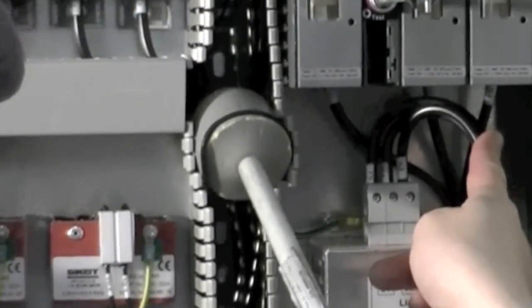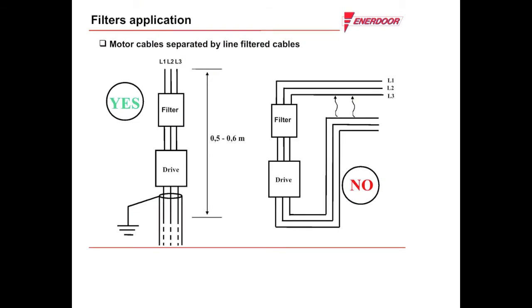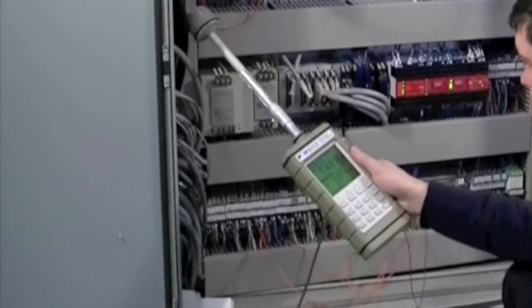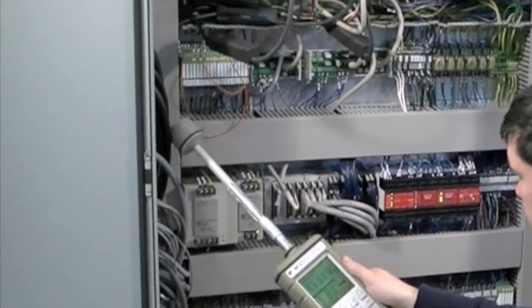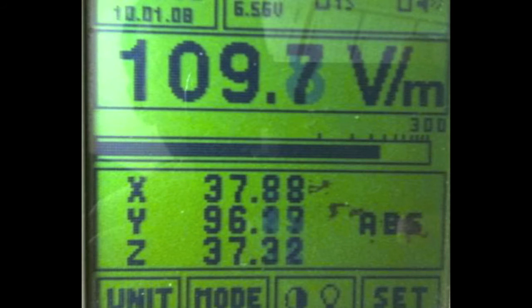Enerdoor works with their customers until they find the best possible solution. Enerdoor also tests the radio frequency coupling inside the cabinet. We look for any cables positioned close to the source of the noise — VFD and drives — and provide suggestions about the best position of the cabling and EMI RFI filter to best minimize the coupling and other future noise issues.